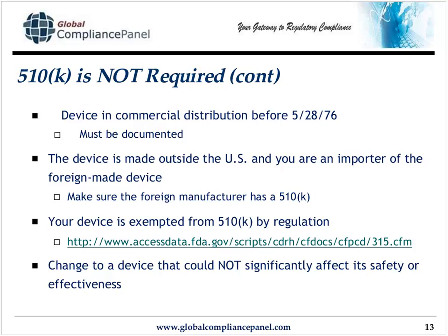There are some devices that are exempt from 510K by regulation, and here's the location to those. When you find your device, make sure it says exempt from pre-market notification submission, and therefore no 510K is required. And last, a 510K is not required if you change your device, and the change cannot significantly affect the device's safety or effectiveness.